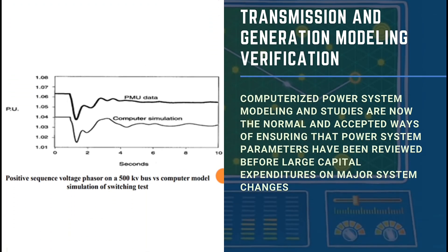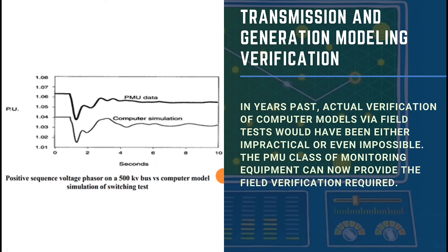Transmission and generation modeling verification: Computerized power system modeling and studies are now the normal and accepted ways of ensuring that power system parameters have been reviewed before large capital expenditures on major system changes. In years past, actual verification of computer models via field tests would have been either impractical or even impossible. The PMU class of monitoring equipment can now provide the field verification required. The shown figure compares a remote substation 500 kV bus voltage captured by the PMU to the stability program results.